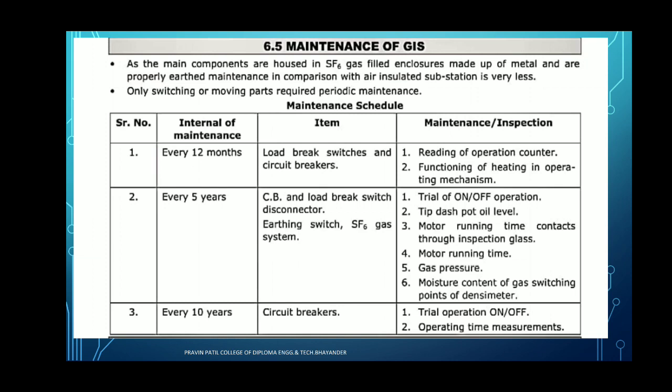After every 5 years, we have to check the circuit breaker as well as the load break switches. It may also include the disconnector, so we have to check the isolator. Then, earthing switches. We have to check the SF6 gas — sulfur hexafluoride gas — systems. We have to check these things every 5 years. The inspection includes: trial of on and off position of the device, meaning we can easily check the continuity of the supply — whether it is workable or not.